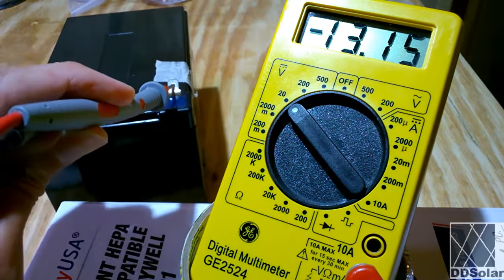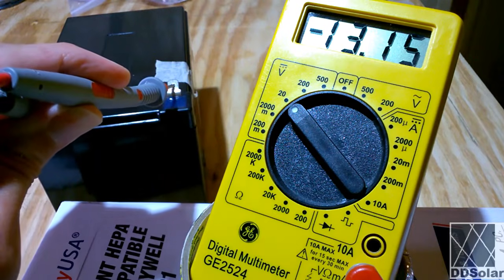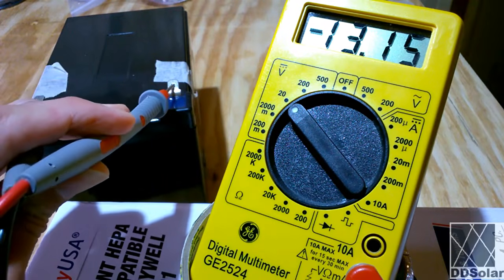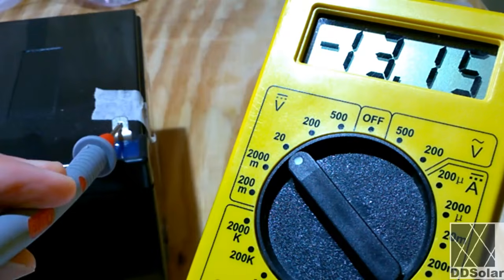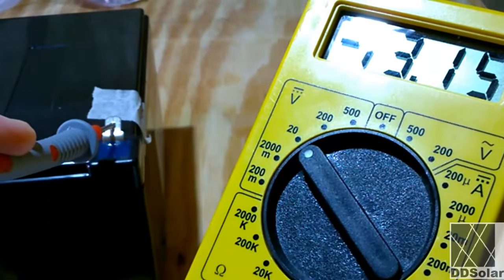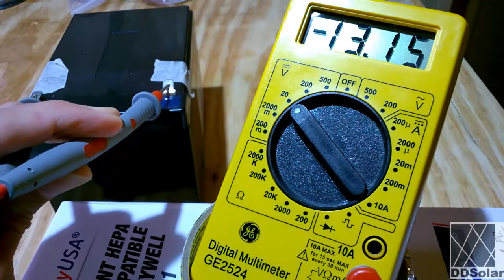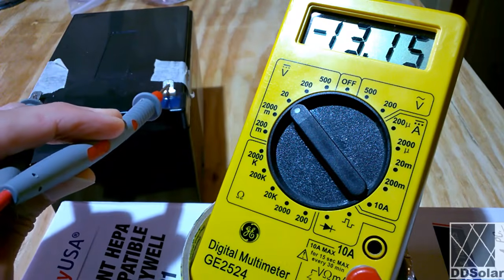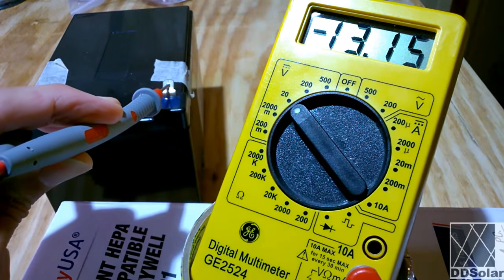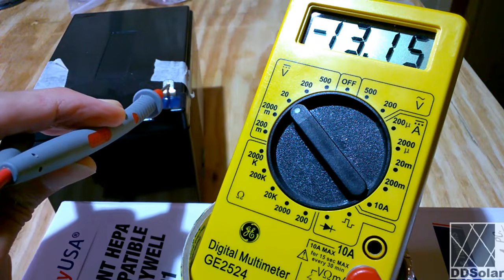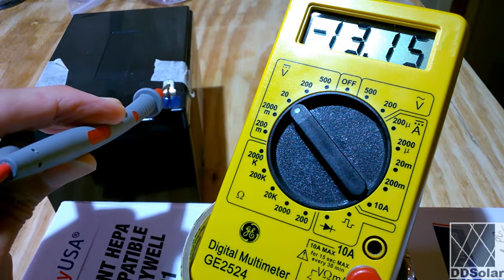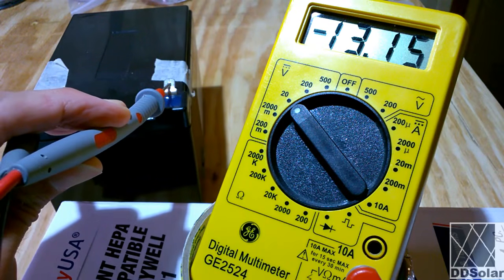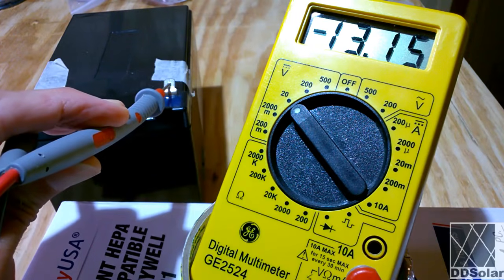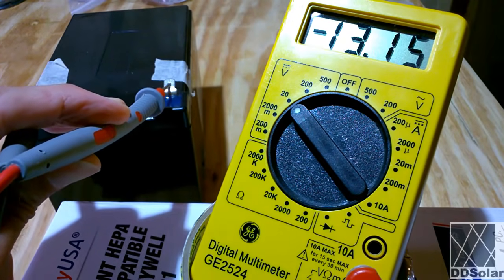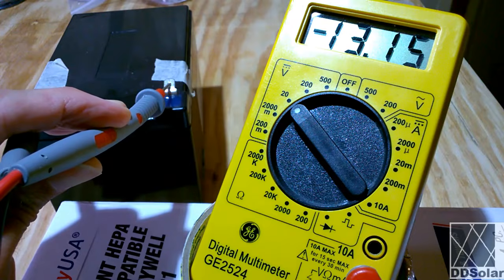And this is one of the most useful functions of a multimeter. It says negative 13.15 volts. Now, as you can see, I've got the red probe positive on the negative of the battery, and I've got the negative probe on the positive side. So, of course, it's now telling me the polarity is backwards. This is by far one of the most useful functions of a multimeter. It's called a polarity check. If you're not sure which is positive and which is negative, this meter could save you $1,000 simply by telling you, hey, don't hook that up backwards.